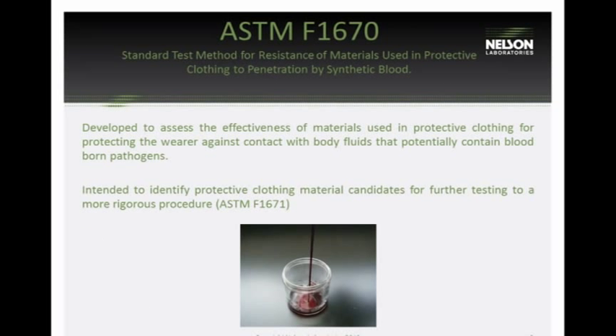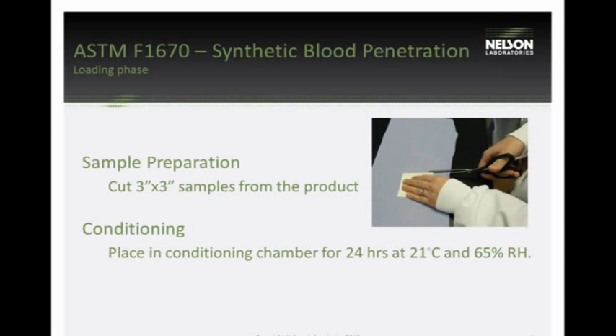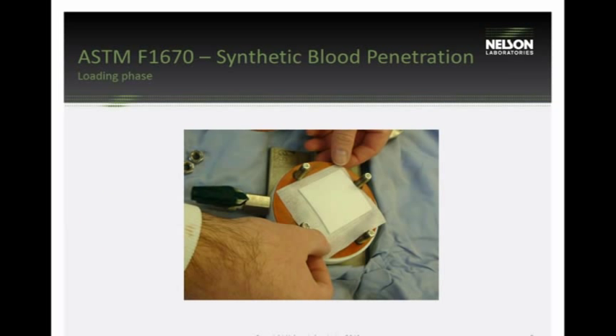The first test method is a gown and drape barrier test called ASTM F1670, or synthetic blood testing. This test method was designed to test the product against penetration by blood and body fluids. It's a precursor test to the viral penetration test. It uses synthetic blood adjusted to mimic real blood — the viscosity, surface tension, and density have all been matched to real blood. The test entails cutting samples into 3-inch by 3-inch squares, conditioned for 24 hours at 21°C and 65% relative humidity prior to testing.